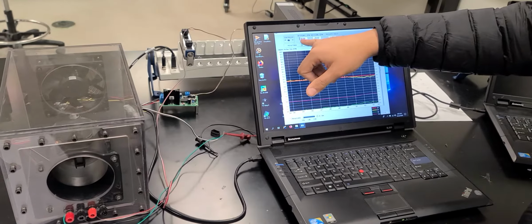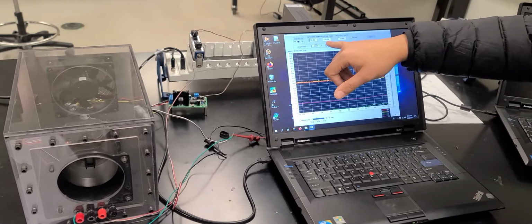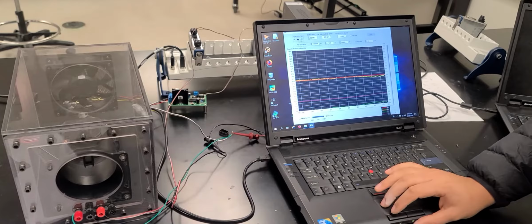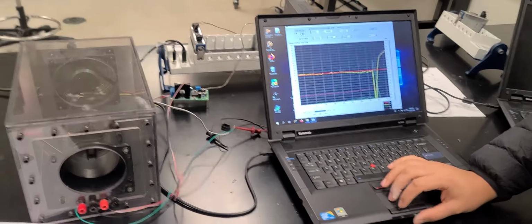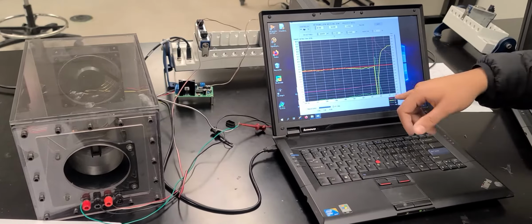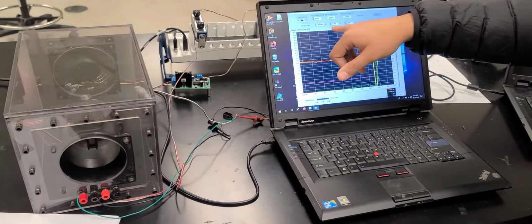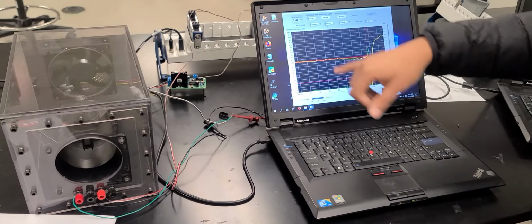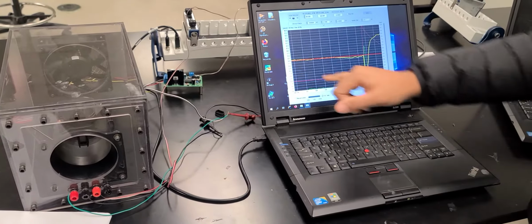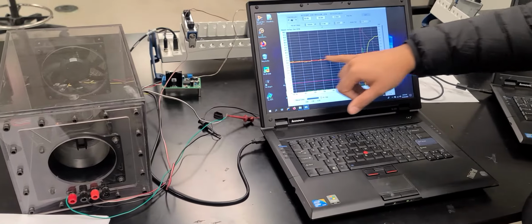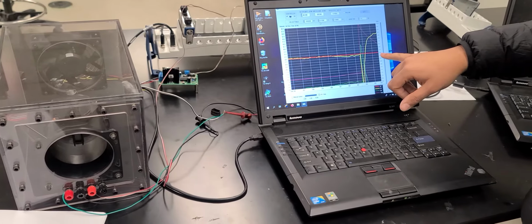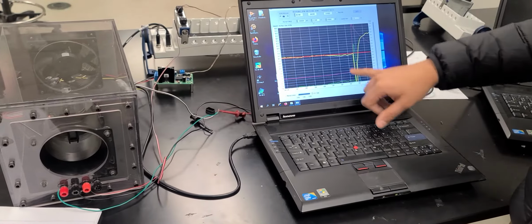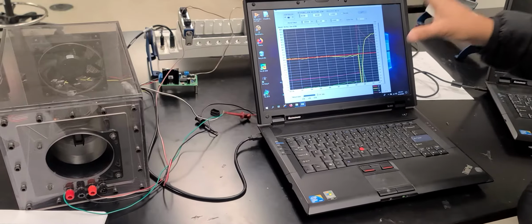You can set your flow rate here. This is the flow rate that you are reading at any time. At this point, it must be 0. You see the flow rate. And then these are the coefficients you're going to change. Right now, we have the coefficients 1, 0.01, and 0. Okay? Kc, Ti, Td. The red line here shows your set point, right? We have set it to be 30. And the yellow line here is the response. But this is just for your visualization.